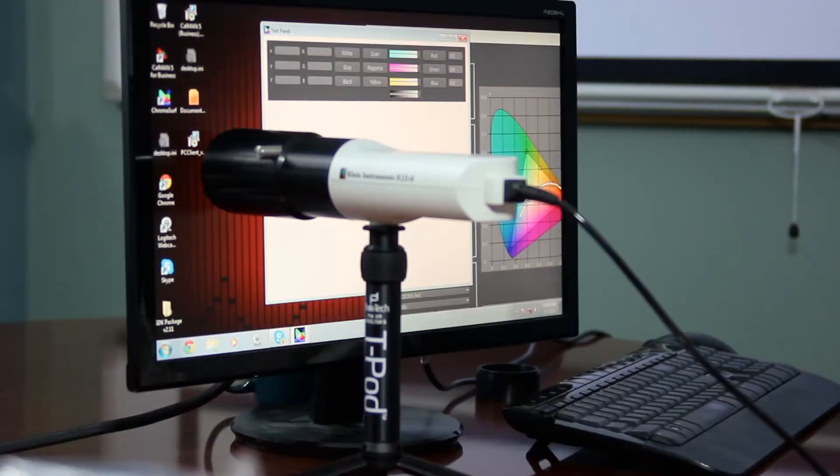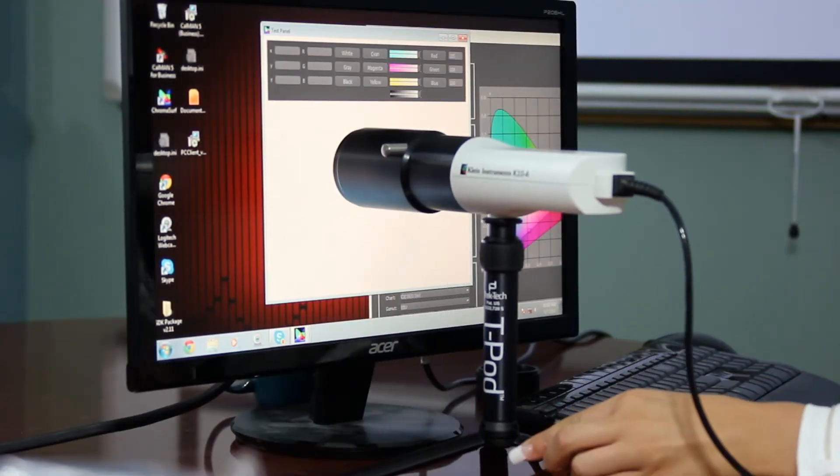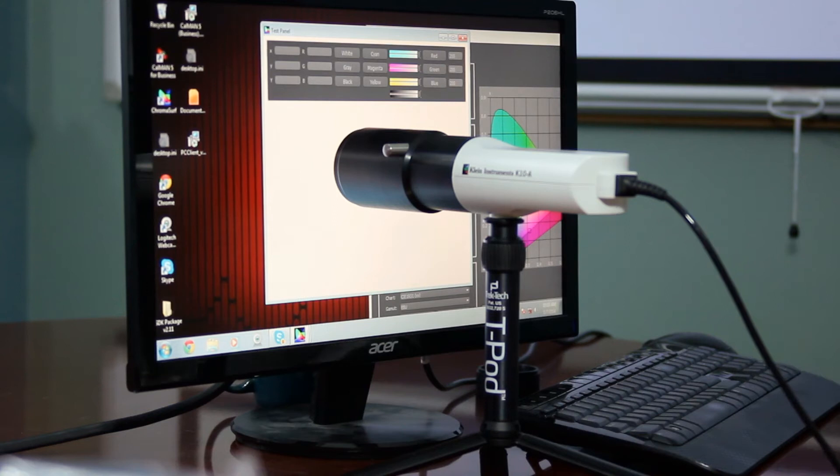Let's start with the K10A, our best-selling colorimeter, and measure a desktop monitor. You generally want to position your K10A near the center of the screen because the intensity tends to fall off near the edges.